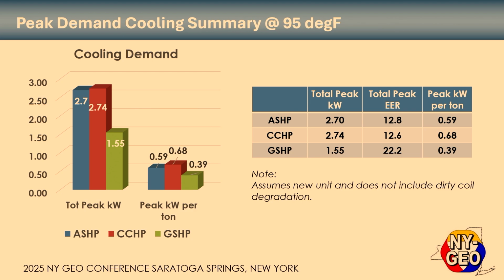And of course, here's the ground source heat pump, and we're operating at a much more moderate temperature. And also we have the ability to get a little bit higher efficiencies with water. So you can see that there's a big difference there. Not quite half, but about 60% or so. So if you go down to peak kW per ton, these are the kind of numbers you would see for that.